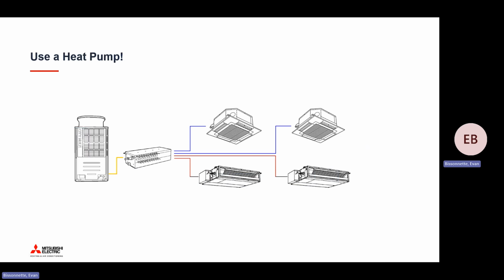Use a heat pump. That's kind of the best option right now. These are all electric systems that are rated down to minus 31 degrees. This is a traditional heat recovery system. So it uses refrigerant to move energy with electricity around your building. So for spaces that are in cooling, we're removing that heat from those spaces with refrigerant, and we're bringing it either to other spaces or outside, or if they're all in heating, we're using the energy outside to move into the building to provide that heat. The issue with these systems is they're not always the best option for your building. So these would be connected to indoor fan coils, and are not always the best application for your building.